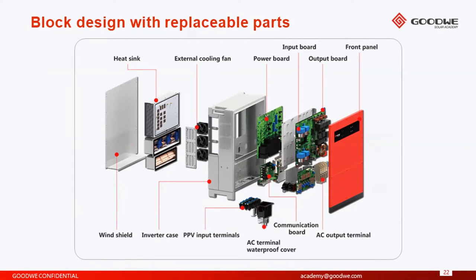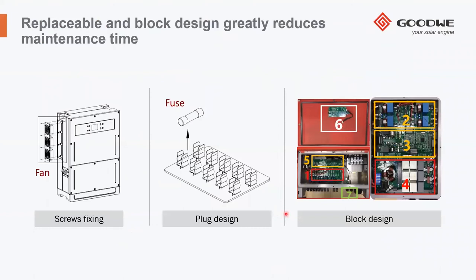And because of this, from the operational point of view, you have a big saving, because as an example, you can easily dismount the fans, and these can be easily replaced without affecting the normal functioning of the system. But also the fuses can be replaced with a plug-in solution, very simple to access, you see here. So you can open the front cover and then you can replace the fuses very, very simply. In case of any failure of the system, basically you can replace the single boards here without changing all the rest of the machine, which means again a big saving in terms of cost and timing for you.